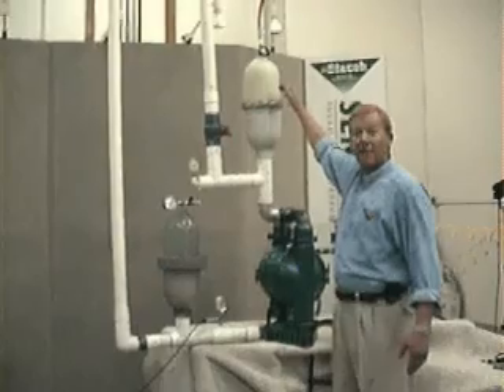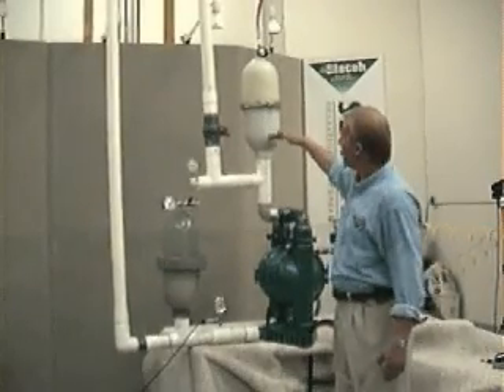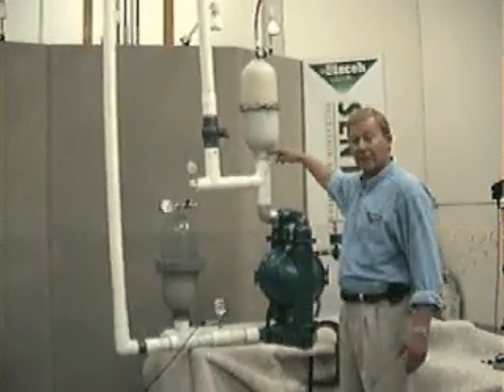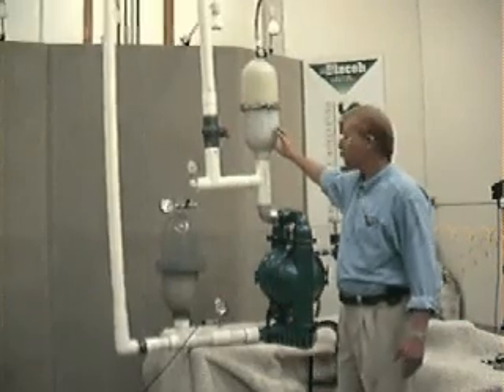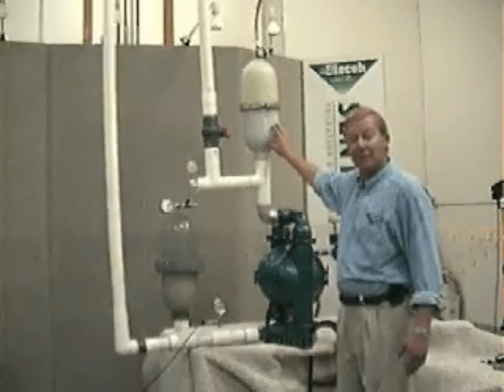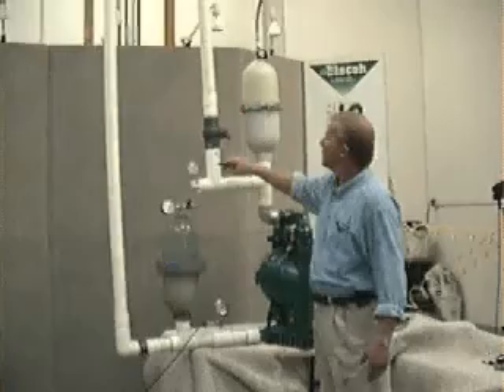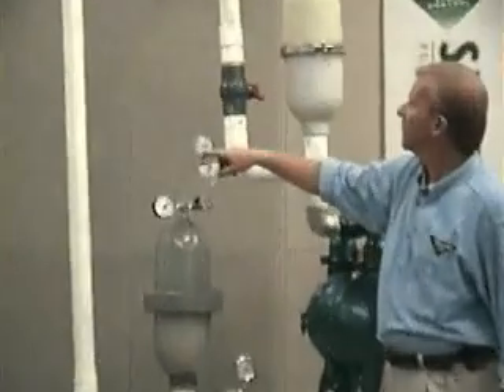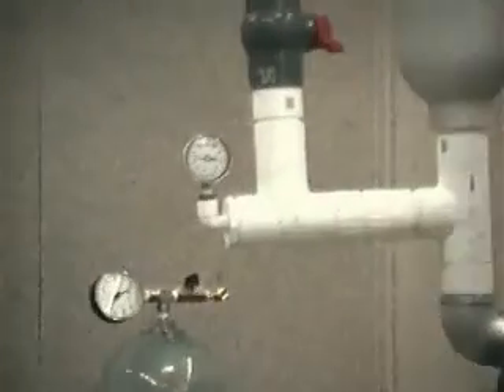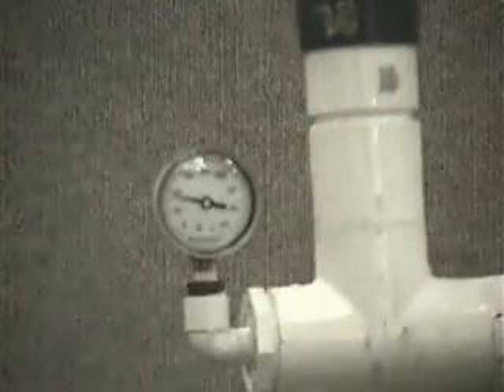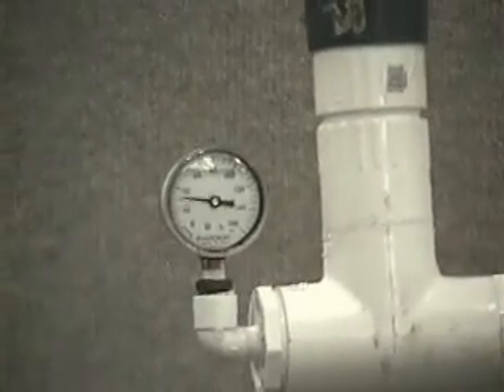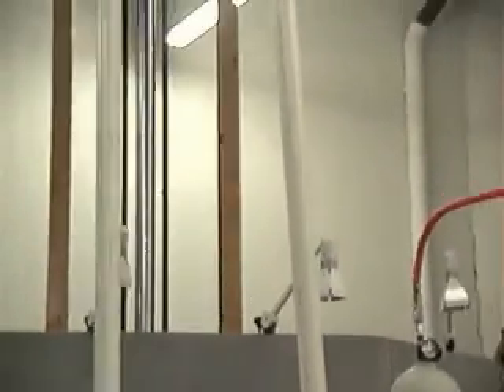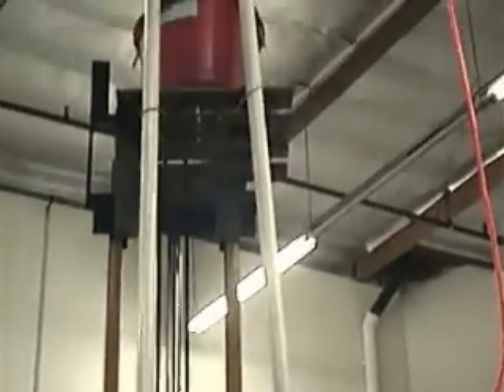The dampeners have been, as I said, overcharged, so their bladders have been pushed down into the inlet and they've shut off. So in effect, they might as well not be in the system. You can see the pulsation occurring at the discharge of the pump, and you'll observe that the discharge flow is pulsing and non-continuous up at the tub.